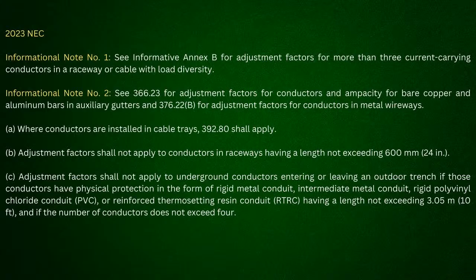So in other words, I could have a whole bunch of cables in there, but not all of them are going to be considered current carrying. So there's load diversity. I could have 40 conductors in there and only 8 of them current carrying. You see what I'm saying? So there's not a lot of heat built up in there. And that's why I have a problem when people say, well, you got to do this and this. Well, no, you need to look at exactly what it's telling you, and you've got to go back and look at other parts of the code. This is using the code as a whole to show where what they're saying is wrong.